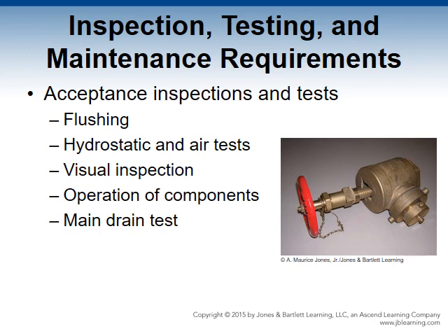This test subjects the system's piping to a 40 psi air pressure over a 24-hour period. A maximum loss of 1.5 psi is allowed over that period. 40 psi is considered the high-end pressure exposed and therefore a good indicator of the integrity of the system.